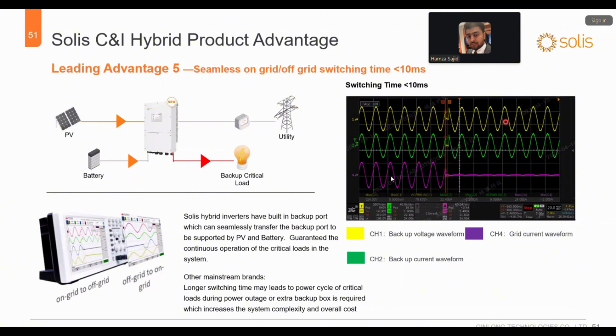So you can see from the waveform, this is the backup port waveform, and this one is the current waveform of the backup port, and this is the current waveform of the grid. So you can see from here, they turned off and the sinusoidal wave started again within less than 10 milliseconds. And from on grid to off grid, and from off grid to on grid, the transition is seamless. So your load is not going to be tripped, even if the grid inverter is tripped from on grid to off grid or off grid to on grid.